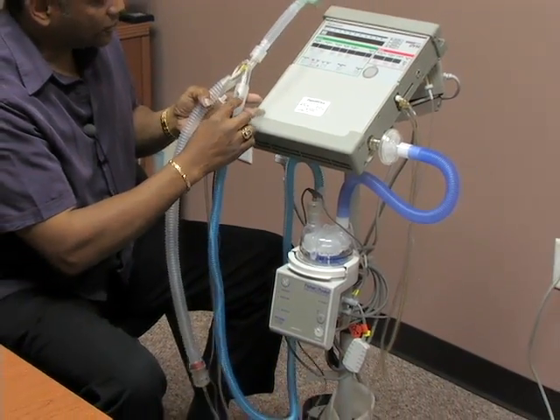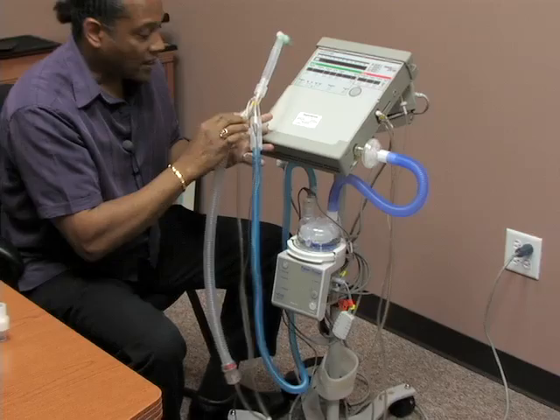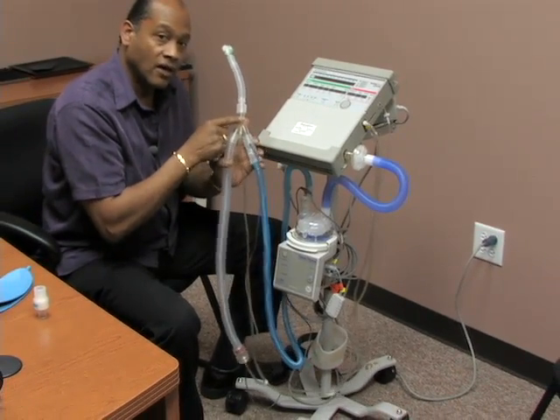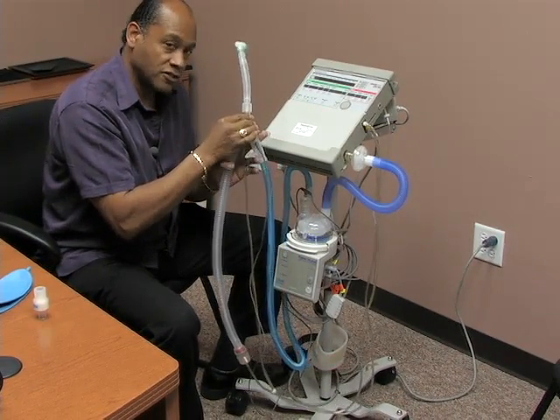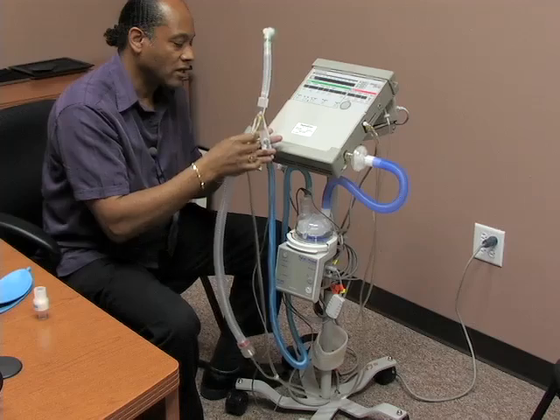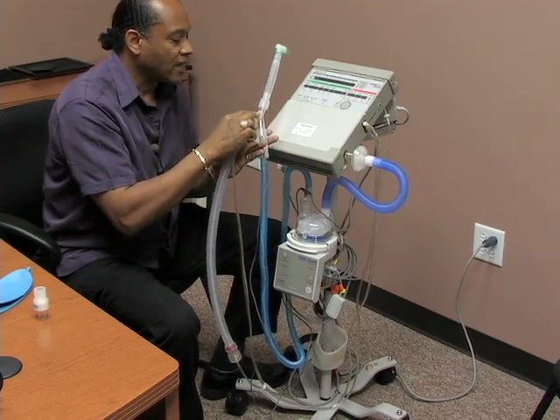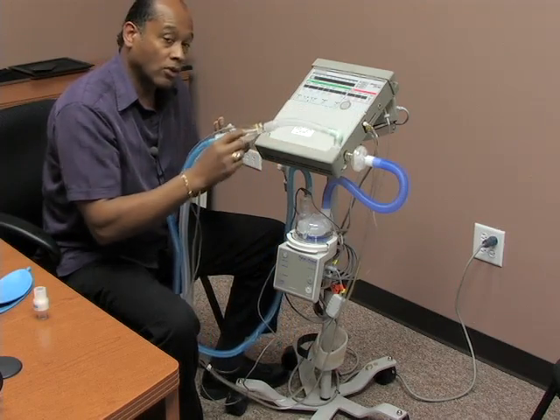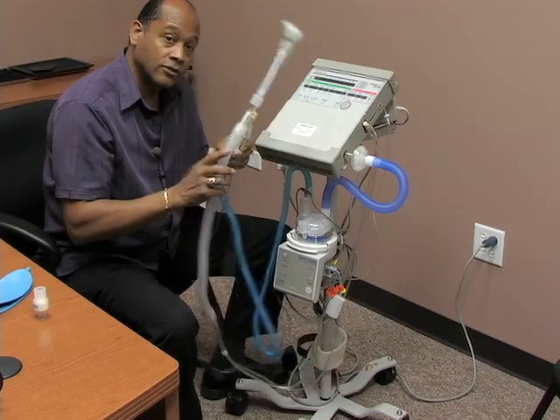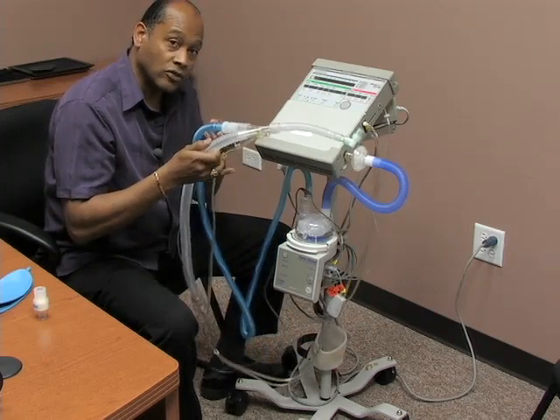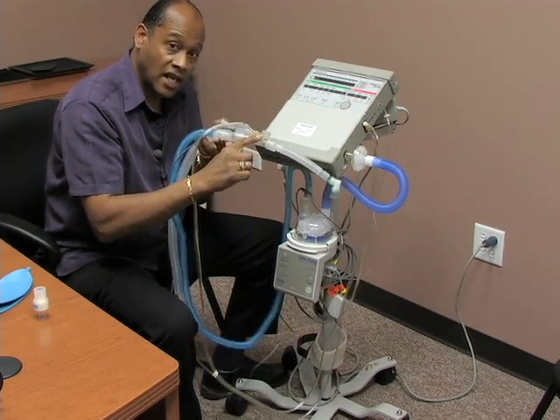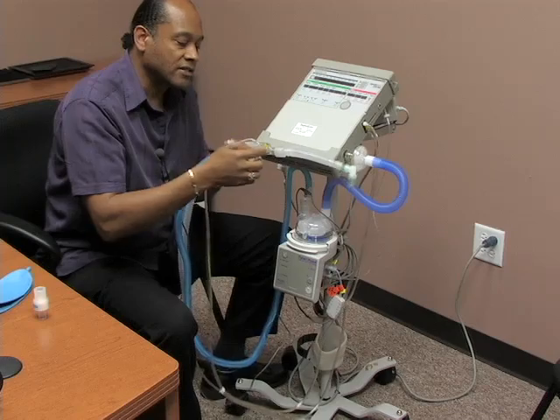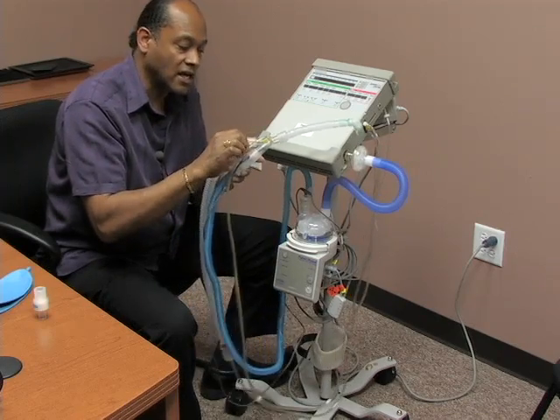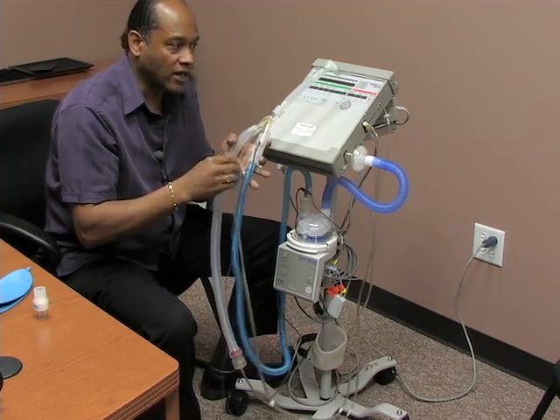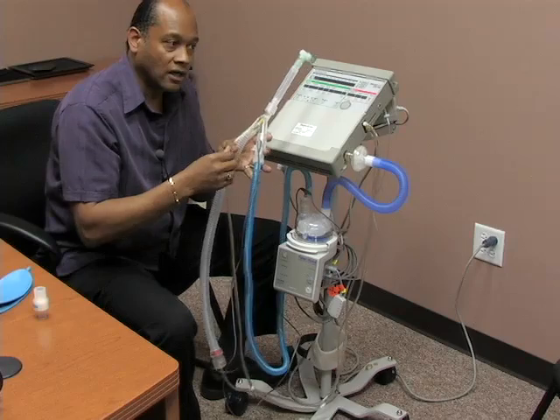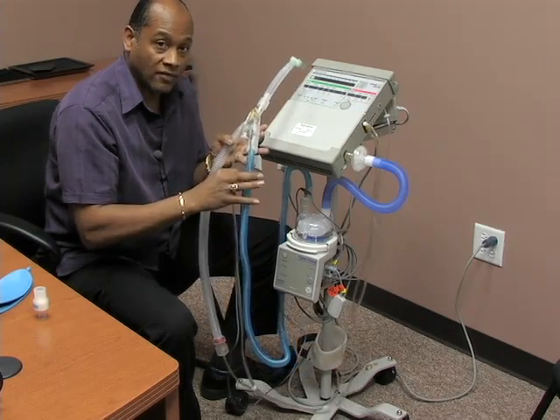The air comes up through to the Y, and this is where all of your readings are actually measured or initially sensed. These are transducer sense lines, and here in the Y are two little ports. It's very important not to place this upside down on your client, but to have the sense lines up. Otherwise, condensation can enter into the sense lines and will confuse the ventilator and cause disconnect alarms, and a lot of other problems.